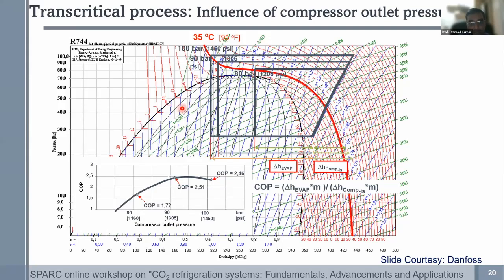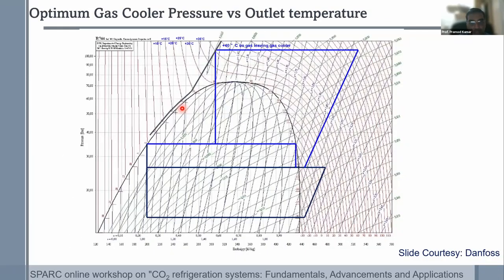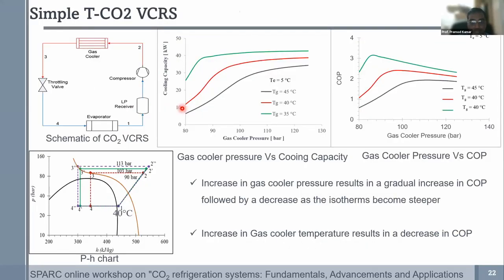Okay. So this is, as the slide says, from Danfoss. This is how the Danfoss controller operates. It continuously monitors the ambient condition and adjusts the compressor discharge pressure. It will command the compressor to continuously adjust its discharge pressure to ensure that you are at an optimum operating point.